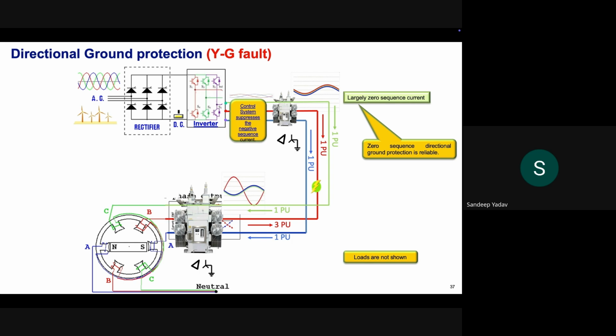If we look at the output of the fault response of the wind farm, we see that the negative sequence current is suppressed by the control system, as we saw in the case of the phase-to-phase fault. So out of positive, negative, and zero sequence, the negative sequence has been suppressed by the controller, and all we get is this zero sequence current because of this delta winding. We know that a delta winding in a transformer acts as a source of zero sequence current. So all we see is zero sequence current in the fault current fed by the wind farm. So it will be the same in all three phases.